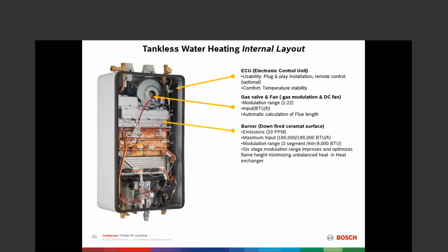The burner is down fired, with 3 segments to that burner, and it fires over 6 different stages of firing, 6 different combinations. The primary heat exchanger is copper, and I know some people think, oh, copper, it's not durable. The copper is very, very durable. And the copper does a great job of energy transfer, very efficient on energy transfer, and it is also a very ductile metal. So as we have very cold water and very hot water, we still get the durability of that metal.